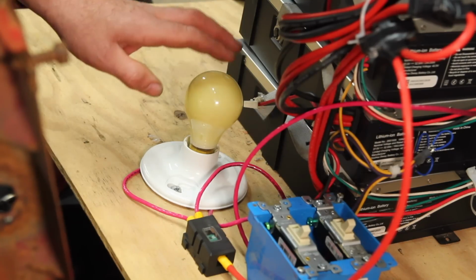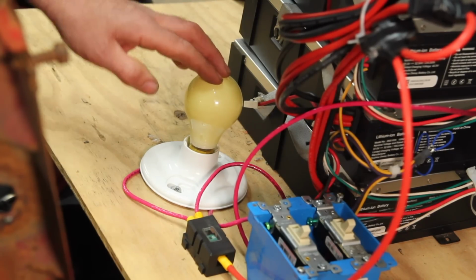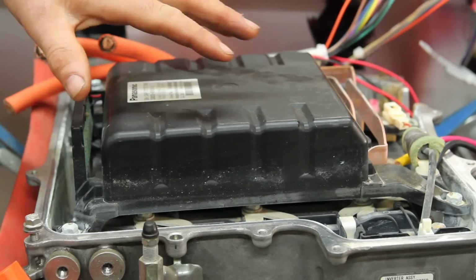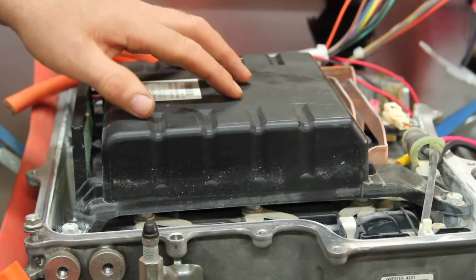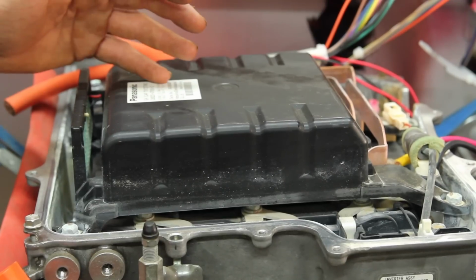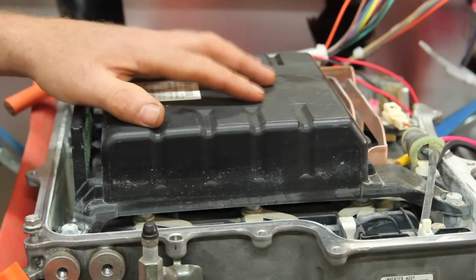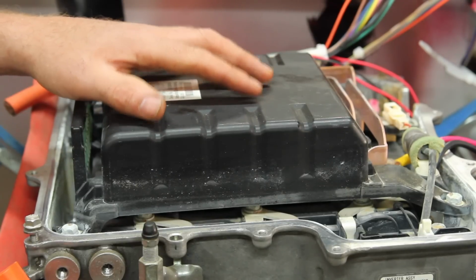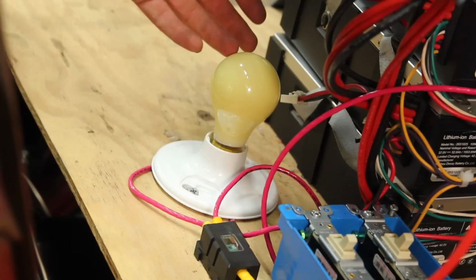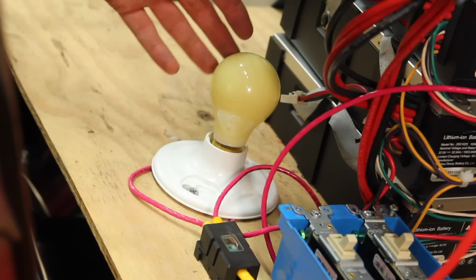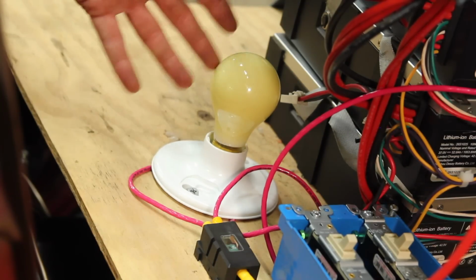This is going to serve as a pre-charge resistor. The inverter has a massive bank of capacitors on top, and when you first apply power, there's a rapid surge of current into them. You want a resistor in the circuit to limit that inrush current. Similarly, the light bulb will also limit any fault currents if something goes wrong.